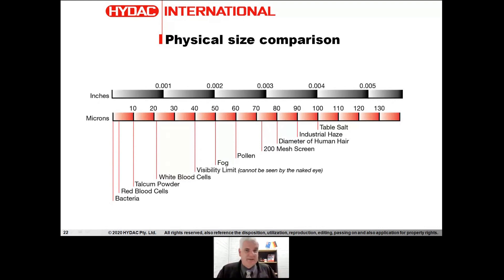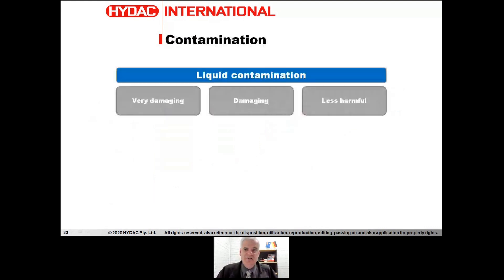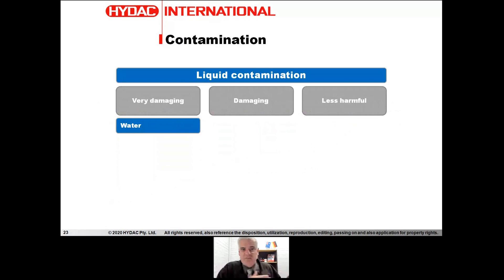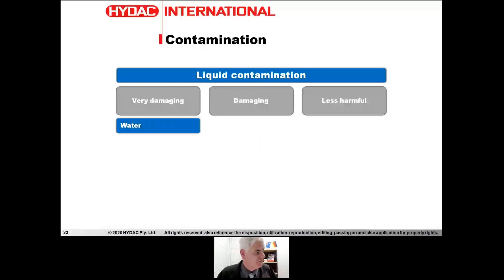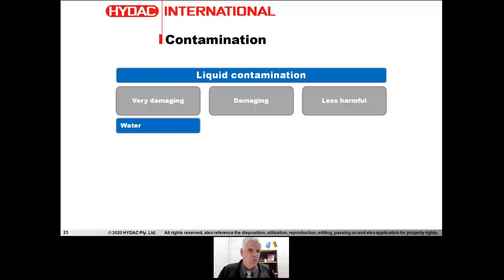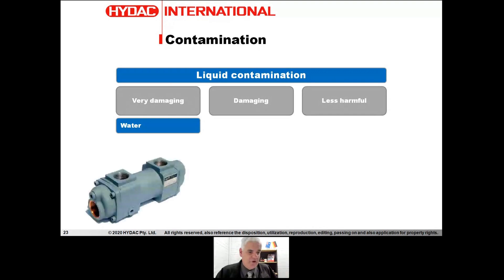That rounds up solid contamination. Now, liquid contamination: the most damaging fluid we can find in these systems is water — very damaging. Water is a poor lubricant and excludes oil, causing a loss of lubricating film. Water causes hydrogen embrittlement of steels, damages bearings, and makes them more susceptible to fatigue. We certainly want to keep water out — as little as possible is the answer to how much we can tolerate.